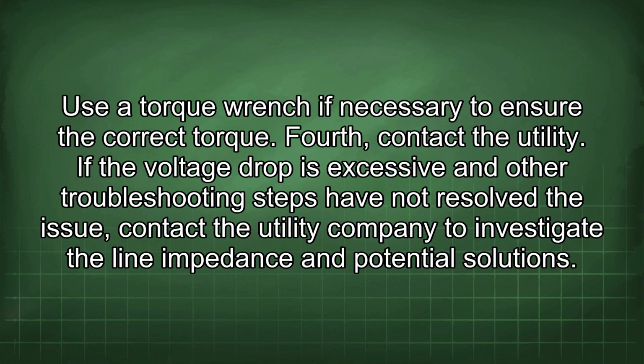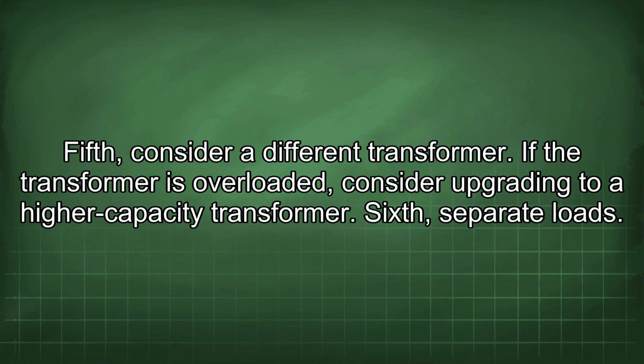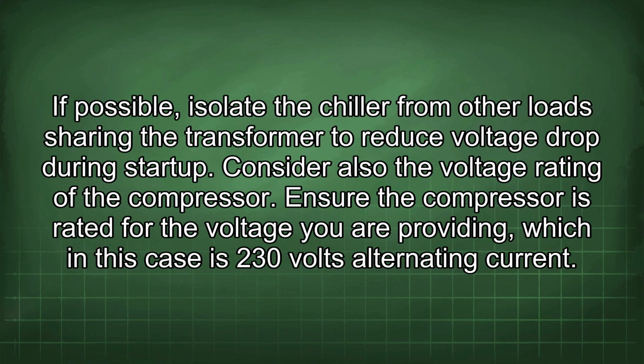Fourth, contact the utility. If the voltage drop is excessive and other troubleshooting steps have not resolved the issue, contact the utility company to investigate the line impedance and potential solutions. Fifth, consider a different transformer. If the transformer is overloaded, consider upgrading to a higher capacity transformer. Sixth, separate loads. If possible, isolate the chiller from other loads sharing the transformer to reduce voltage drop during startup.